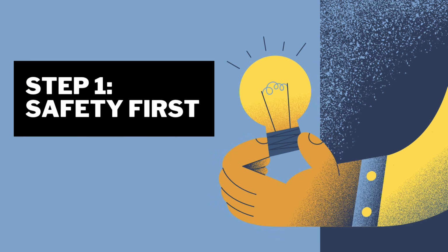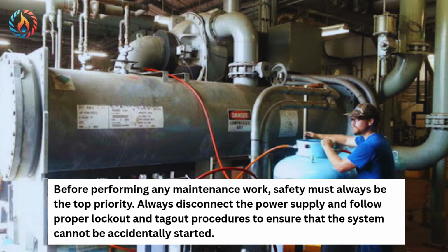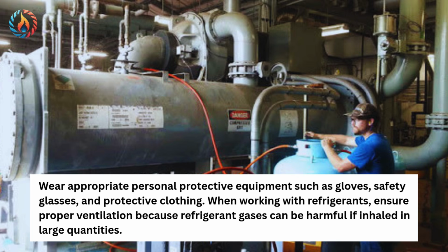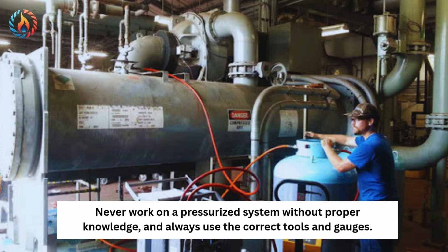Step 1. Safety. First, before performing any maintenance work, safety must always be the top priority. Always disconnect the power supply and follow proper lockout and tagout procedures to ensure that the system cannot be accidentally started. Wear appropriate personal protective equipment, such as gloves, safety glasses, and protective clothing. When working with refrigerants, ensure proper ventilation, because refrigerant gases can be harmful if inhaled in large quantities. Never work on a pressurized system without proper knowledge, and always use the correct tools and gauges.